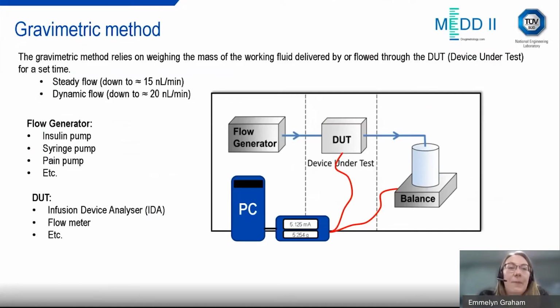So traditionally, the gravimetric method has been used, particularly for higher flow rates, or what we would call maybe microflow rates. You would have your flow generator for drug delivery. This could be an insulin pump, syringe pump, pen pump. We may have a device under test as well, or instead, this could be our infusion device analyzer. I'll explain a little bit more about that later. Or it could be a flow meter, and sometimes you could have a flow meter in your infusion line to be able to monitor. There are limitations with using the gravimetric method, in that it's very difficult to go down and use it for nano flow rates. It's been well established at much higher flow rates.